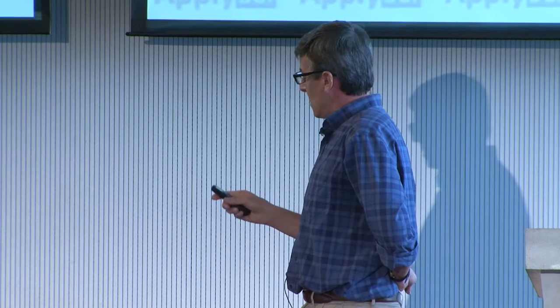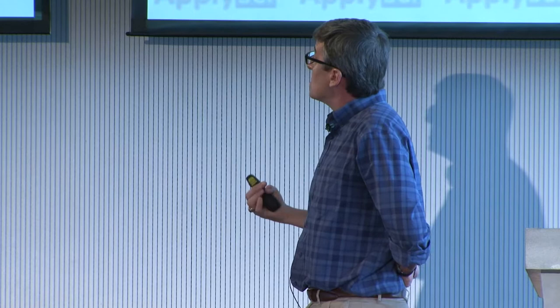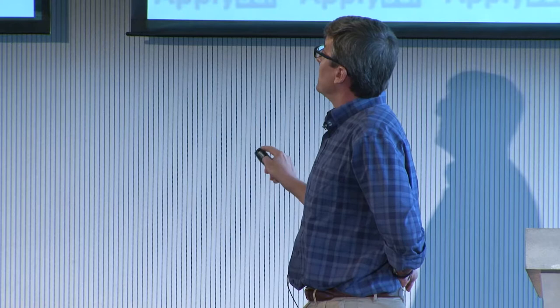It needs to flex, obviously, but it also needs to stretch for two reasons. One, to conform to the complex geometrical topographies presented by the skin and other integration points across the body, but also because these organs and these tissues themselves stretch and undergo deformation. So you have to think beyond mechanical flexibility to elastic stretchability at a strain level in the range of 30%. By comparison, silicon fractures at about a 1% tensile strain.